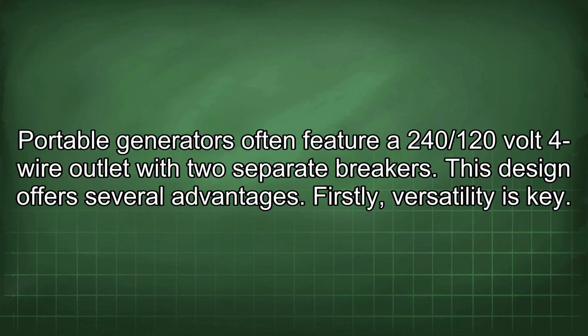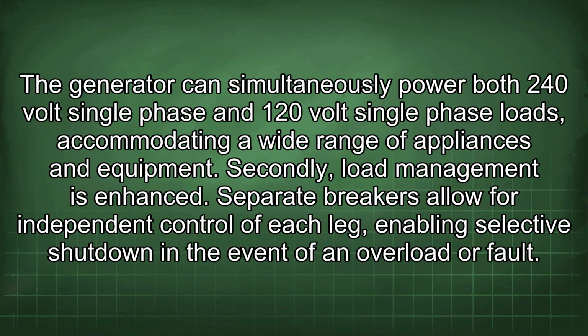Portable generators often feature a 240/120-volt 4-wire outlet with two separate breakers. This design offers several advantages. Firstly, versatility is key. The generator can simultaneously power both 240-volt single-phase and 120-volt single-phase loads, accommodating a wide range of appliances and equipment. Secondly, load management is enhanced.